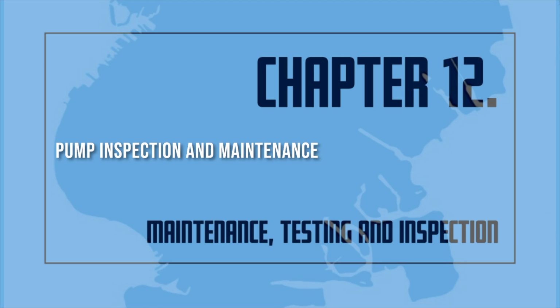If an automatic controller operates the fire pump, the pump shall be activated by reducing the water pressure in the system. This can be done by opening the test drain or initiating a large water flow from the system. By starting the fire pump this way, the certificate of fitness holder can determine if the automatic controller is working properly. Care should be taken to make sure that the pump does not overheat while conducting the test.